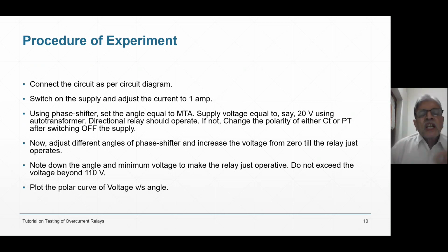What is the procedure? Connect the circuit as per circuit diagram. We have seen the circuit diagram. Switch on the supply and adjust the current to 1 ampere because my relay is 1 ampere. Exactly 1 ampere you adjust. Using phase shifter, set the angle equal to MTA. MTA is given by the relay manufacturer. MTA is a design feature. Theta, maximum torque angle or characteristic angle, is a design feature.